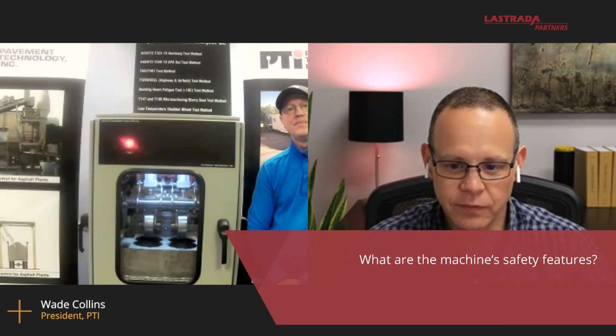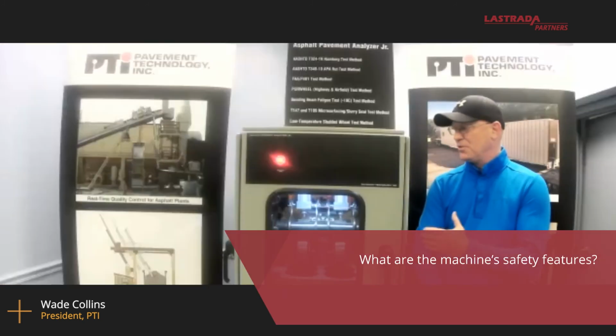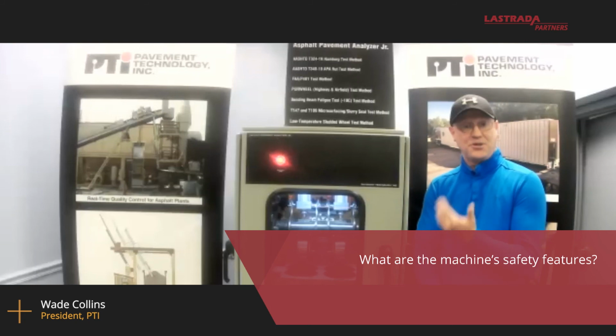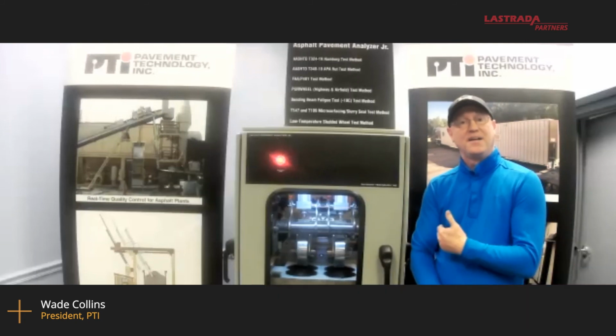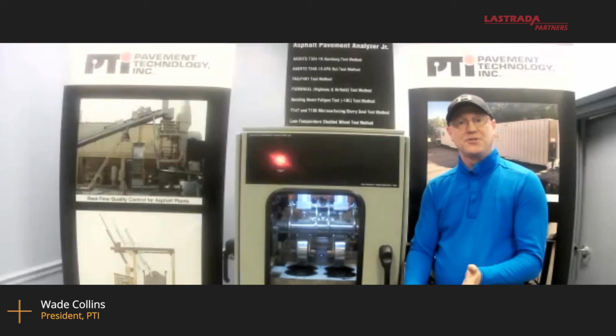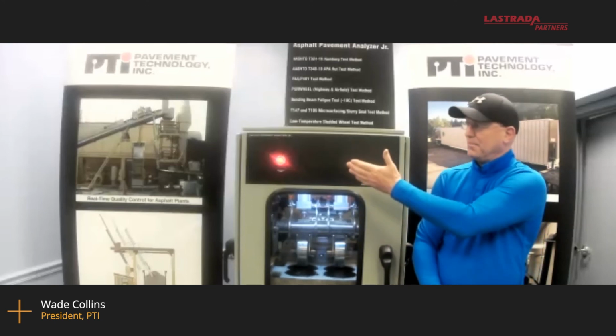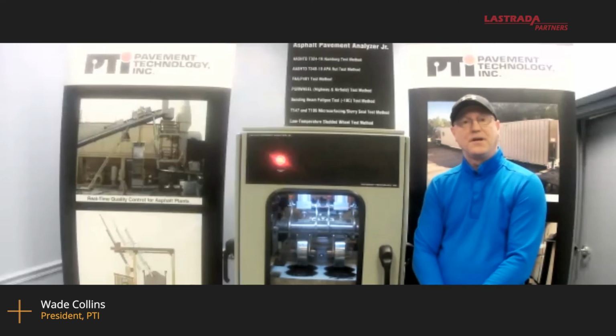What are some of the safety features of the APA Junior machine? The APA Junior has limit switches on each of the doors. Basically, if someone is curious and decides to open up a door, it will terminate operation of the machine. We also have an emergency stop button here on the front, another safety feature - if someone needs to shut the machine off, you have ready access to it on the front panel.